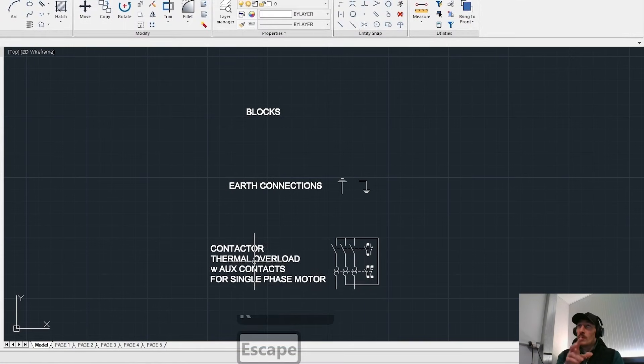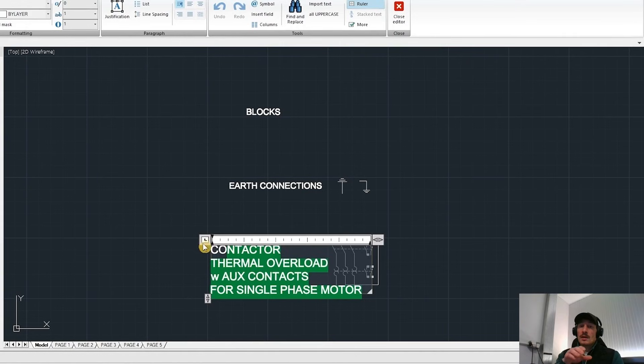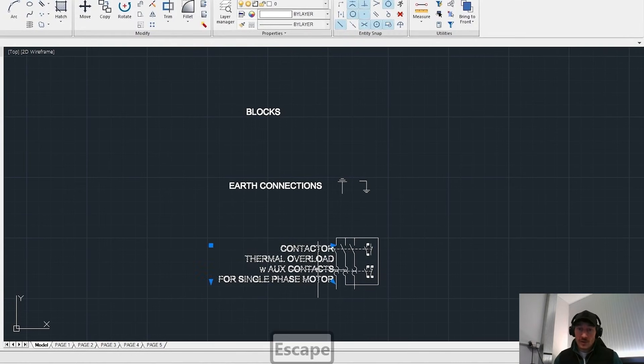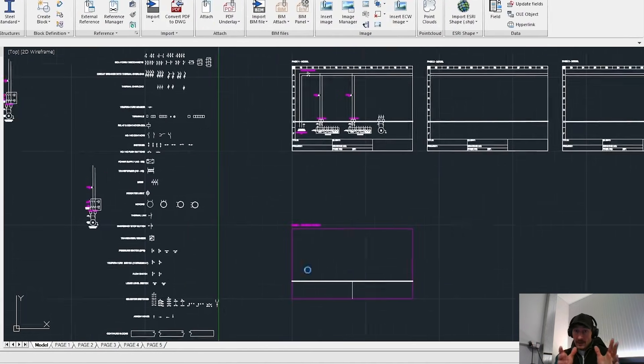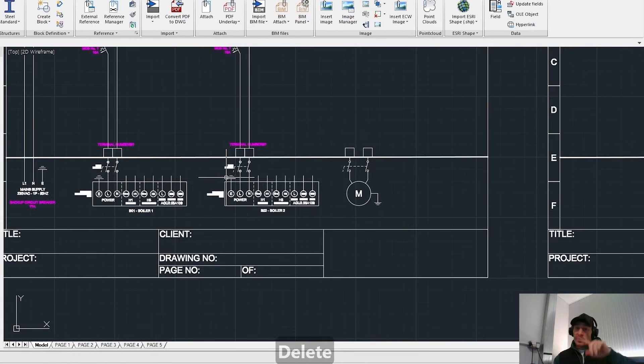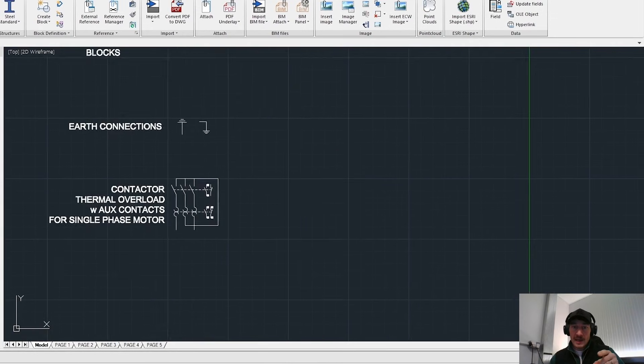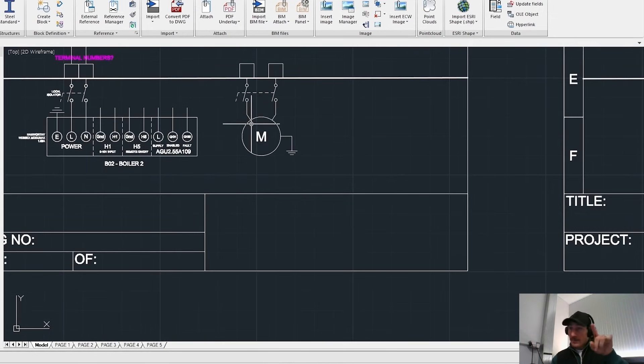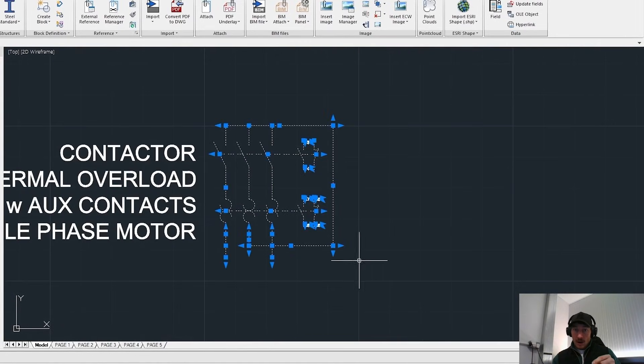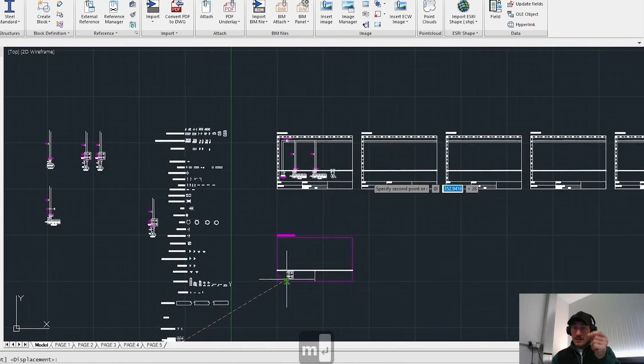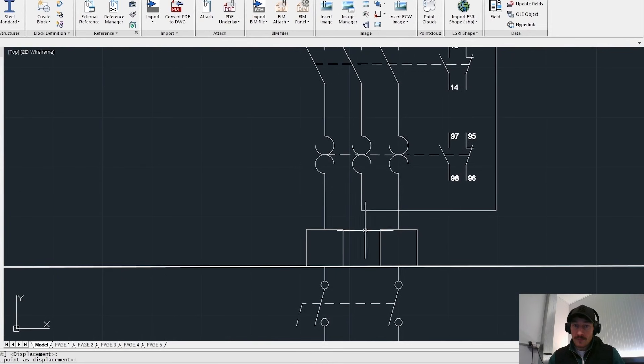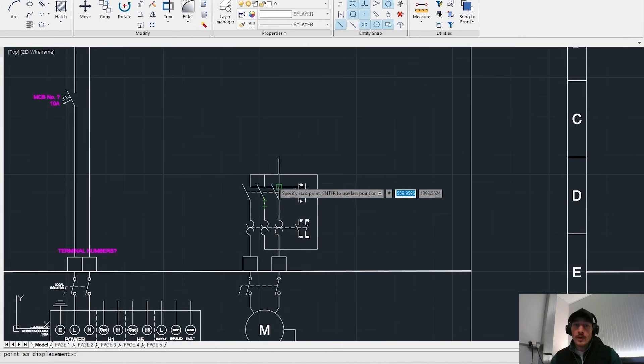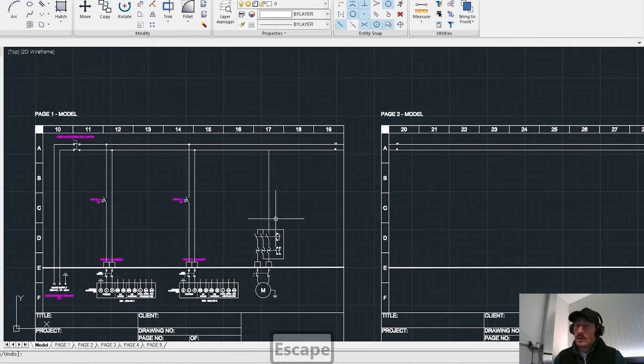These are as you saw with the motor. There is only two cables coming from the motor to that main isolator. So it is a two pole, single phase, it is just a live and a neutral and although we are using a three phase contactor because most of them come in three phase, we are just going to wire it in a way that the live is coming in the contactor out of the overload and then back in to the second pole of the contactor and overload. So we are putting the full load through that overload relay so it works correctly.